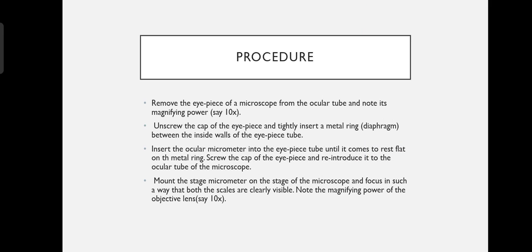to stage micrometer. Micrometric calibration involves finding out the absolute distance on the stage micrometer corresponding to one division of the ocular micrometer scale. From this, the value of one division in the ocular micrometer can be calculated. This value is called a micrometer value or calibration factor. It is done only after superimposing the graduations of the ocular and stage micrometers. Focusing of the stage micrometer will cause the superimposing of the scale of the ocular micrometer over the scale of the stage micrometer. Now the values are compared and the number of divisions on the ocular scale equivalent to each division of the stage micrometer is calculated. The ocular scale value is converted to stage micrometer value. During this operation, the ocular micrometer has been calibrated against the stage micrometer.